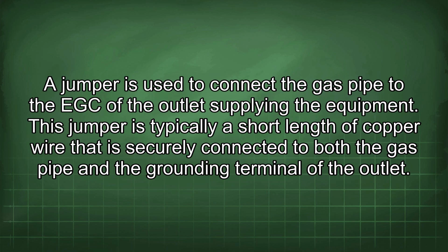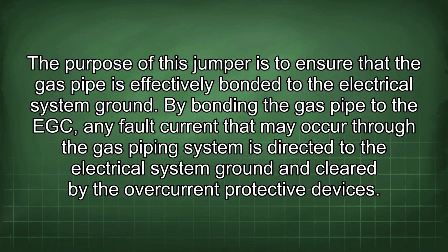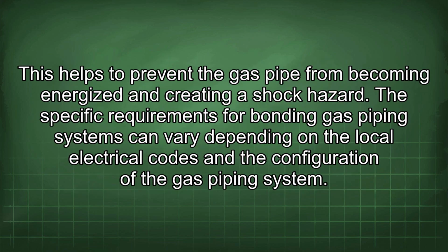A jumper is used to connect the gas pipe to the EGC of the outlet supplying the equipment. This jumper is typically a short length of copper wire that is securely connected to both the gas pipe and the grounding terminal of the outlet. The purpose of this jumper is to ensure that the gas pipe is effectively bonded to the electrical system ground. By bonding the gas pipe to the EGC, any fault current that may occur through the gas piping system is directed to the electrical system ground and cleared by the overcurrent protective devices. This helps to prevent the gas pipe from becoming energized and creating a shock hazard. The specific requirements for bonding gas piping systems can vary depending on the local electrical codes and the configuration of the gas piping system.